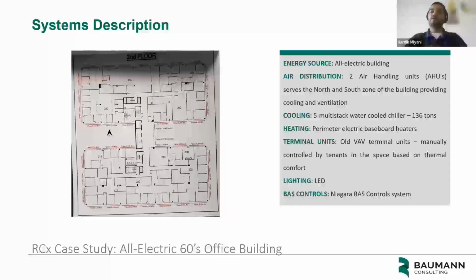Since the building was a 1960s construction, they have very old VAV terminal units, which means they are manually controlled by the tenants in the space depending upon thermal comfort. Suppose the tenants are feeling too cold, they will just close the damper manually to restrict the amount of cold air coming from the VAV terminals. And if they are feeling too hot, they will just open up the dampers. So they have very old VAV terminal units. All the lighting is LED, and they had a BAS control, that is a Niagara BAS control system. This is something that we can also see in office buildings in the DC market as well. We will be seeing a very similar construction in buildings from the 1960s, with almost the same type of HVAC system.